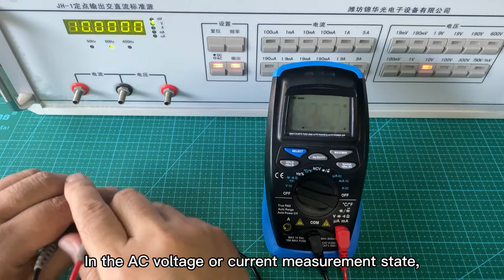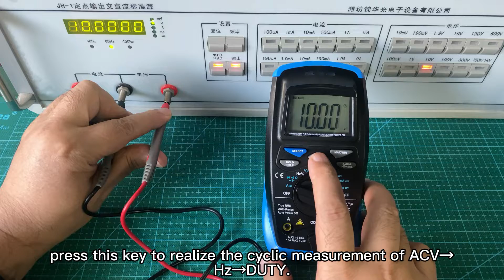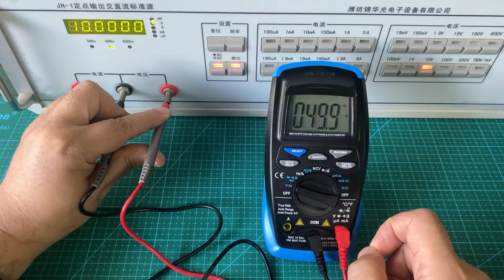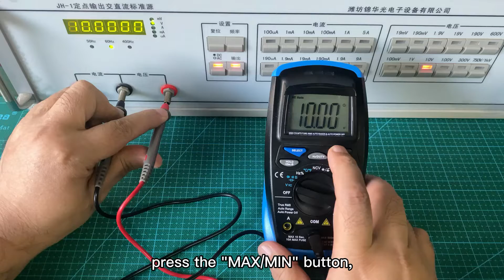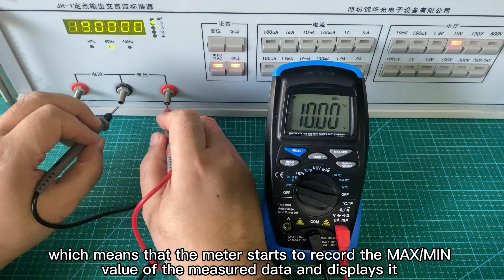Frequency, duty cycle key. In the AC voltage or current measurement state, press this key to realize the cyclic measurement of ACV, Hz, duty. Max, min button. Press the max min button. The meter displays the max symbol, which means that the meter starts to record the maximum value of the measured data and displays it on the LCD screen.